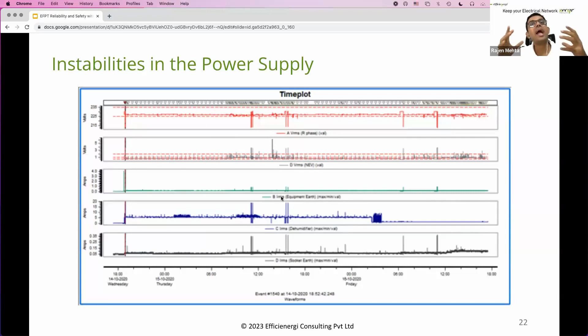You see here the socket earthing, where a significant amount of leakages were found, and we had ground potentials rising to almost 5 to 10 volts when there was a correlation with certain dehumidifiers etc. coming into the system. So these are some of the issues which we recognized and identified through this multi-location and holistic electrical network health study.